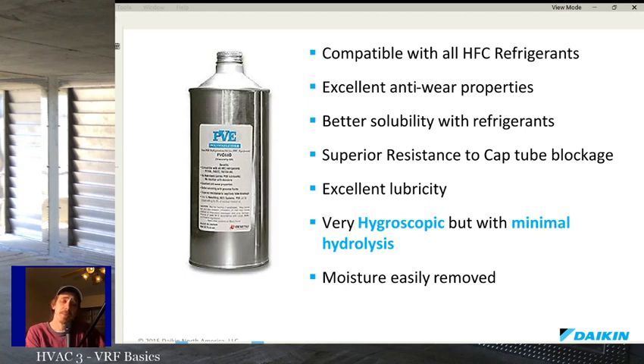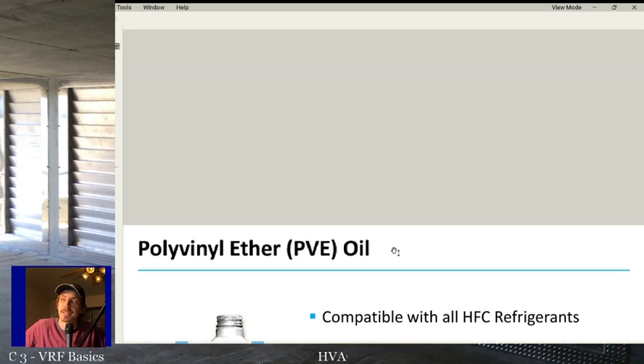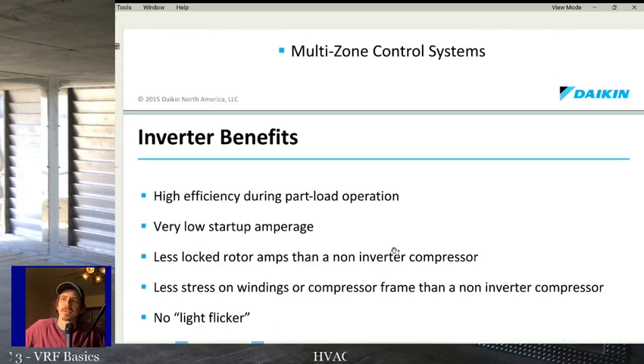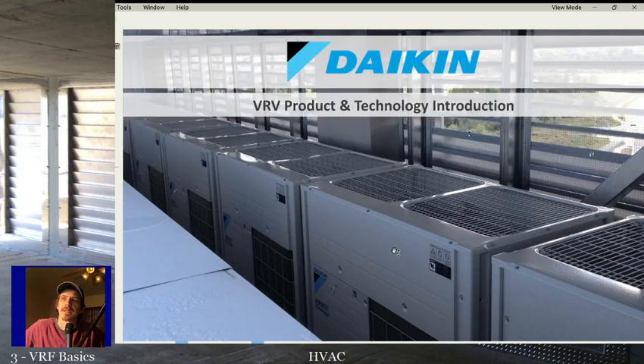So with the heat pump VRF, it's still just a suction line and a liquid line. There's nothing super complicated about it, other than you're going to use Ys to split off to the indoor units, and the whole system has to be in heat or cooling. What I'm going to focus on more when I'm talking about VRF right now is the heat recovery. So instead of a heat pump system, which is all the units in cooling or all the units in heating, a heat recovery system can do simultaneous heating and cooling, if I can find my words. So a heat recovery system can do simultaneous heating and cooling at the same time.